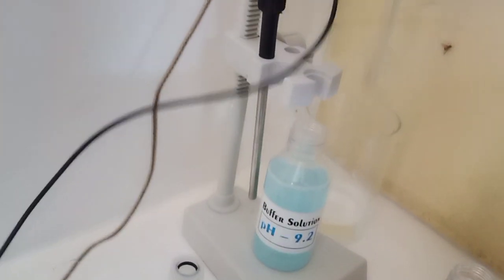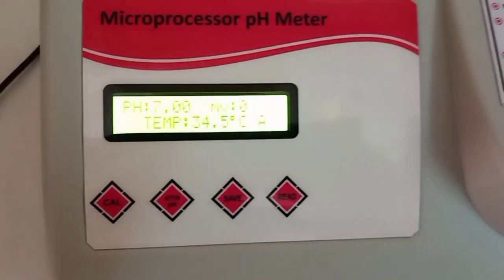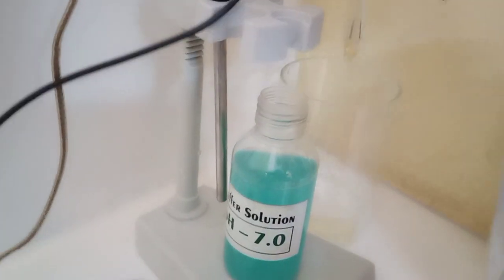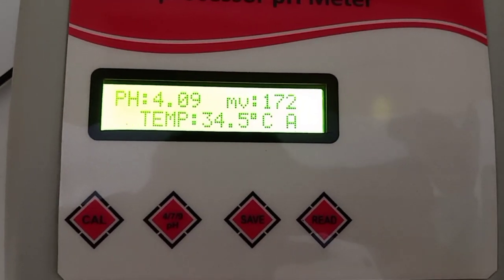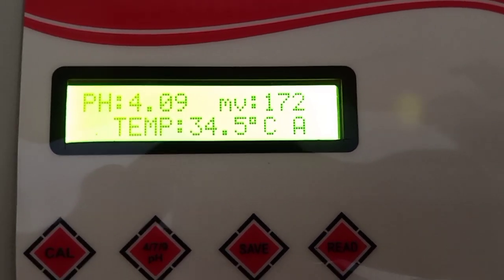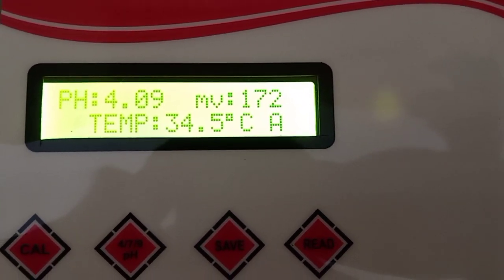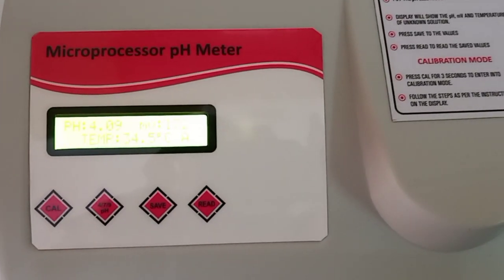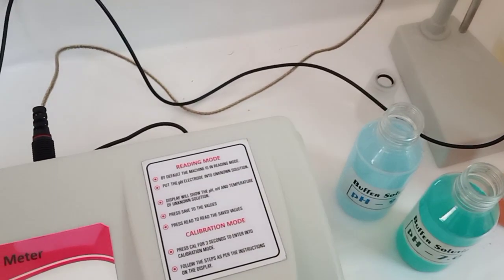Now wash the electrode thoroughly using the distilled water and put electrode into any other buffer, say 7 pH. Now the machine showing 7 pH value. After that, wash thoroughly the electrode with the distilled water and put electrode into 4 pH. After that, the machine is ready for taking any sample.